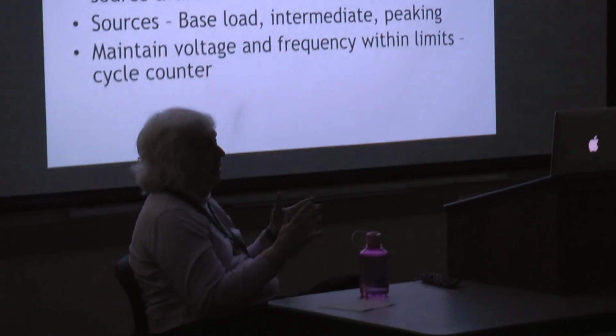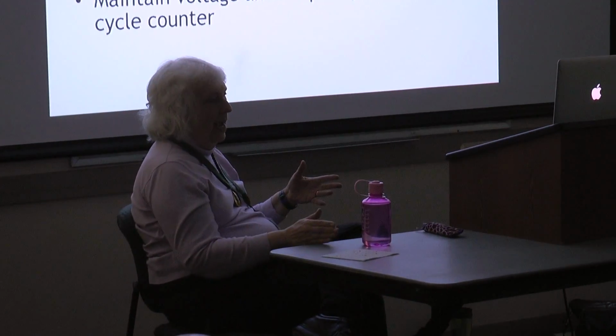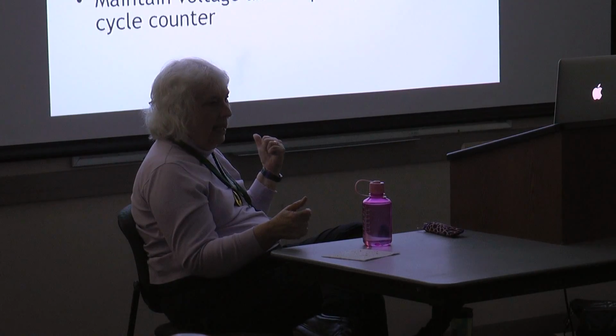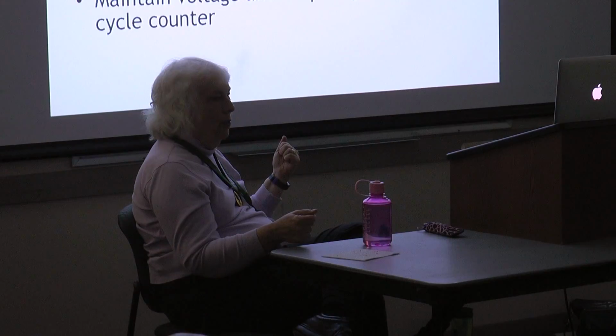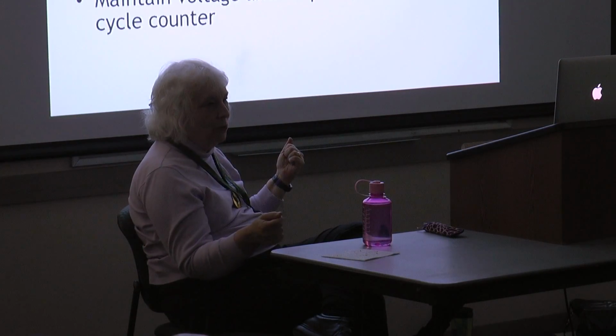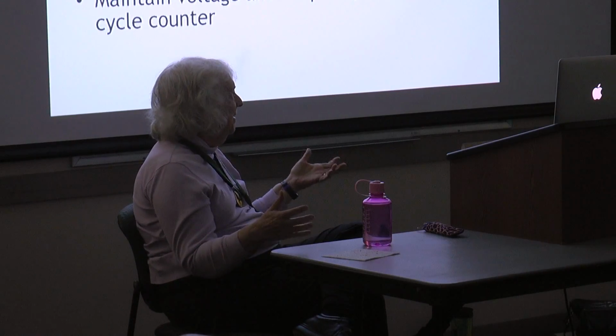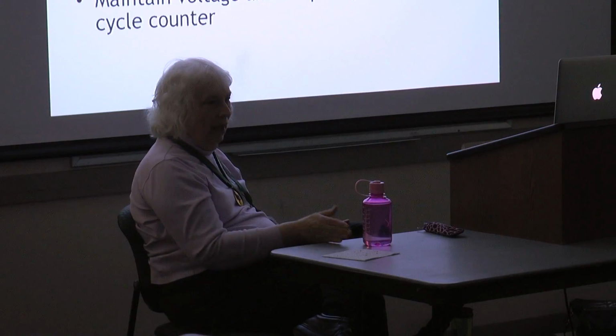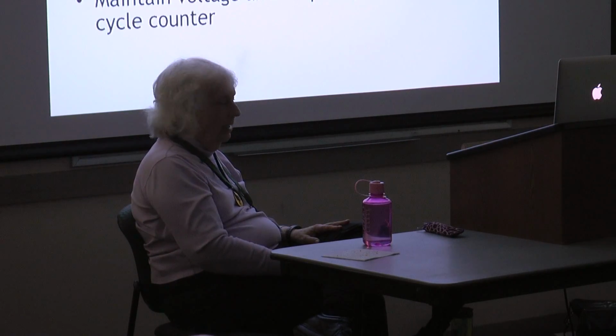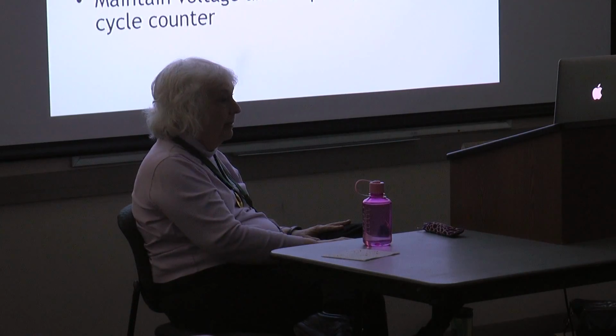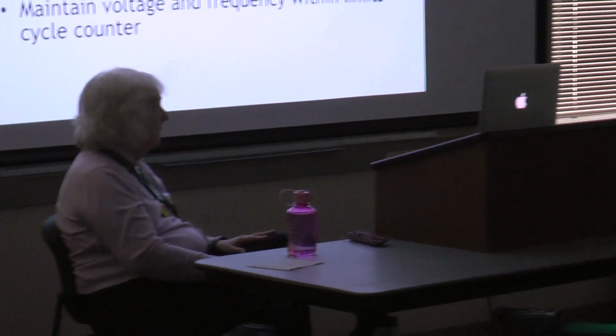I just want to say that what Howard is saying, and it's important, and I don't really understand it, is that you have to have different levels of backup. You have to have the spinning reserve, like that gas turbine that can go on really fast, but then you don't want to have gas turbines that are 120% of the largest source of your material that will be all spinning. So there's a lot of different levels of backup to the grid. I mean, to what has to be done to keep it going. Yeah, and we could ask that when we go to ISO New England too. A little more about that spinning reserve and what happens in that first 10 minutes. That would be maybe a little dip in frequency and voltage on the transmission lines and being picked up by things that are already running.